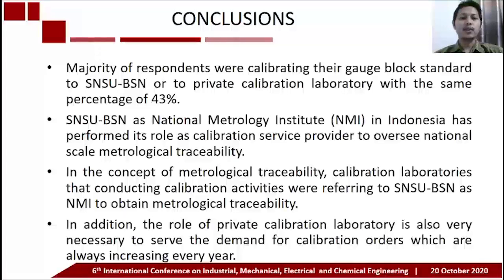In the concept of metrological traceability, calibration laboratories conducting calibration activities refer to SNSU-BSN, the NMI, to obtain the metrological traceability chain. In addition, the role of private calibration laboratories is also very necessary to serve the demand for calibration orders, which is always increasing every year.